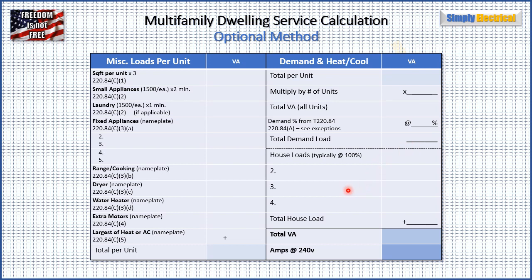If we have any house loads, we would add those here. I treat house loads separately — I actually have another video on that. House loads are done with the standard method, not the optional. For our examples, we'll take our demand load as our total VA, divide by our voltage to get our amps and service size, which we can then use to size feeders, conduit, and meter packs. Don't worry if this is going too fast — that's what this video is about, it's the Crash Course. For more detail, please see my deep dive series where I go through every step meticulously with every code reference.